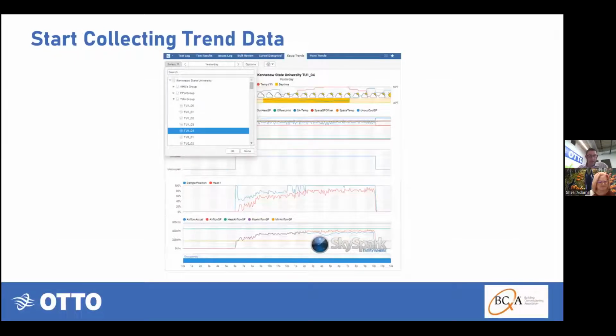Then we're starting to collect trend data, so you can access trend data easily through a pull-down list. We use SkySpark—it provides the best trend viewer I've seen in the market compared to any control system's own trend viewer. They all have trend viewers built in, but for some reason they're just not as easy to work with as the SkySpark trend viewer, shown here. So a couple days after you put in this gateway, you're going to have access to 5-minute interval trend data on 15 to 20 points per terminal unit, and all your air handlers, chilled water plant, hot water plant—whatever it is on the BAS you'd like to see.